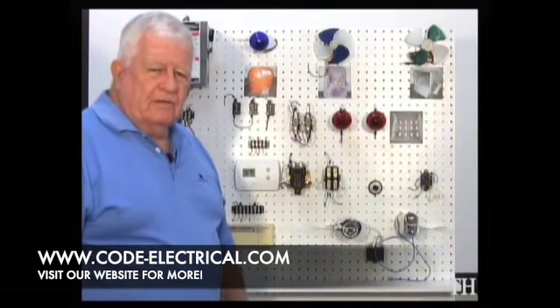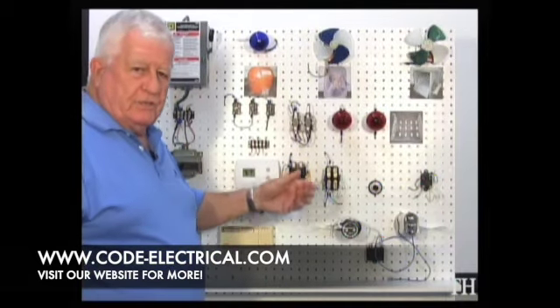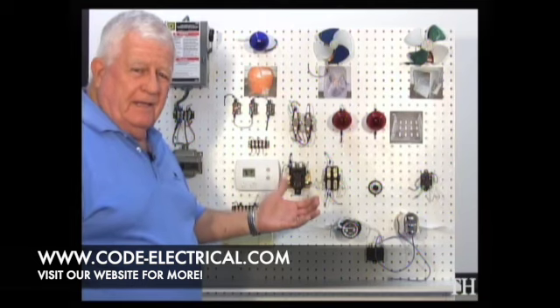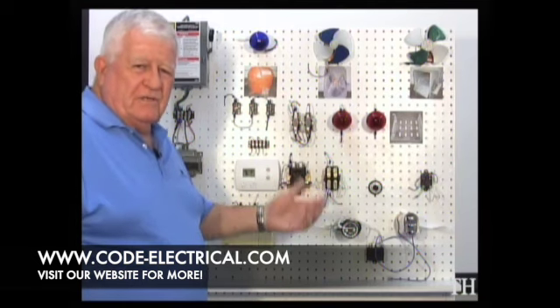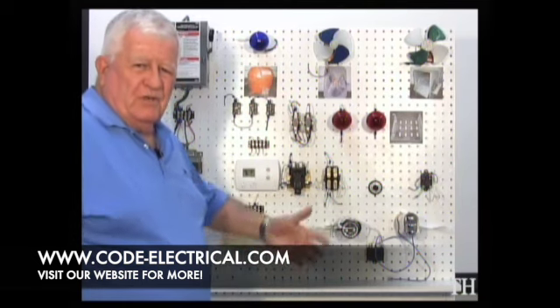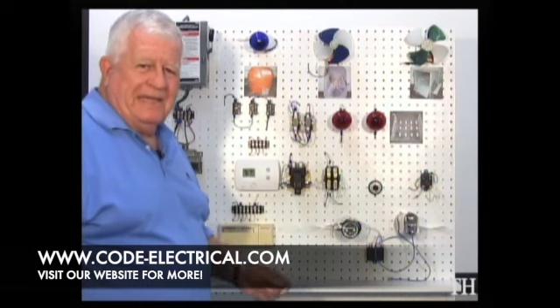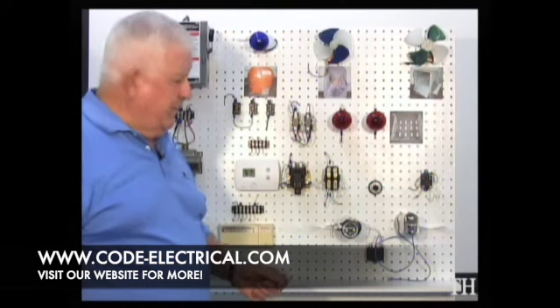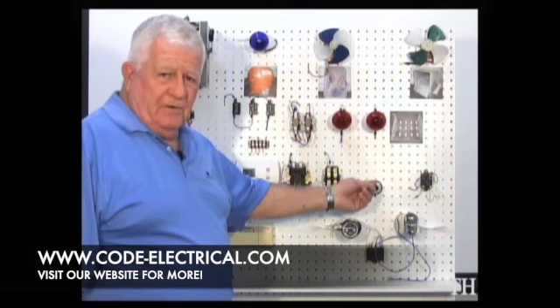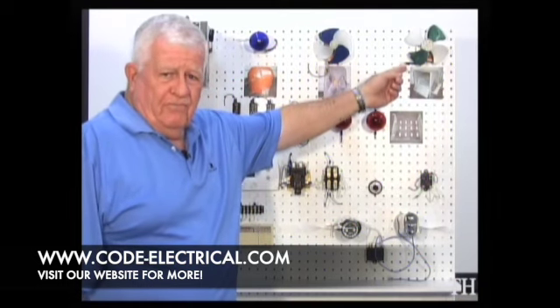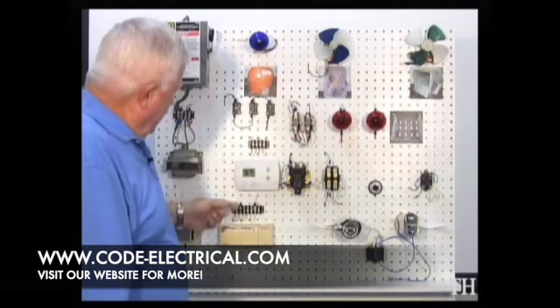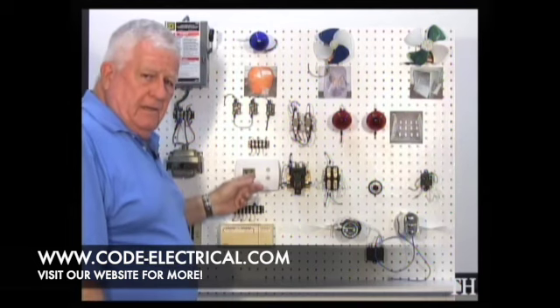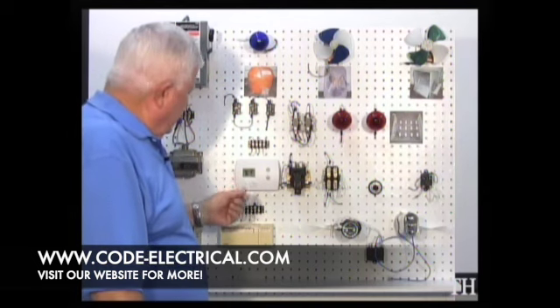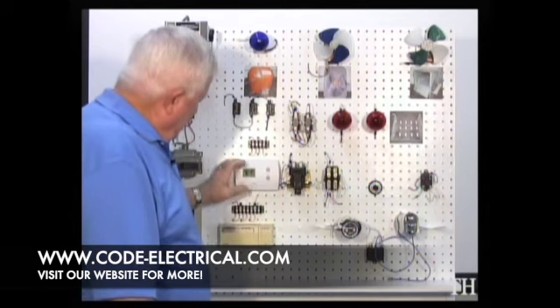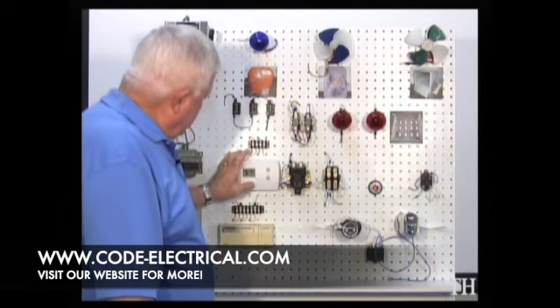What I want to do now is show you the sequence of operation from the thermostat. Say it's the first cold day in the fall and it's getting cool in the house and you need some heat, with a gas furnace. This is our gas solenoid and this is our indoor fan. I'll come over to the thermostat and check the temperature - wow, it's cool in here - so I'm going to flip this to heat.